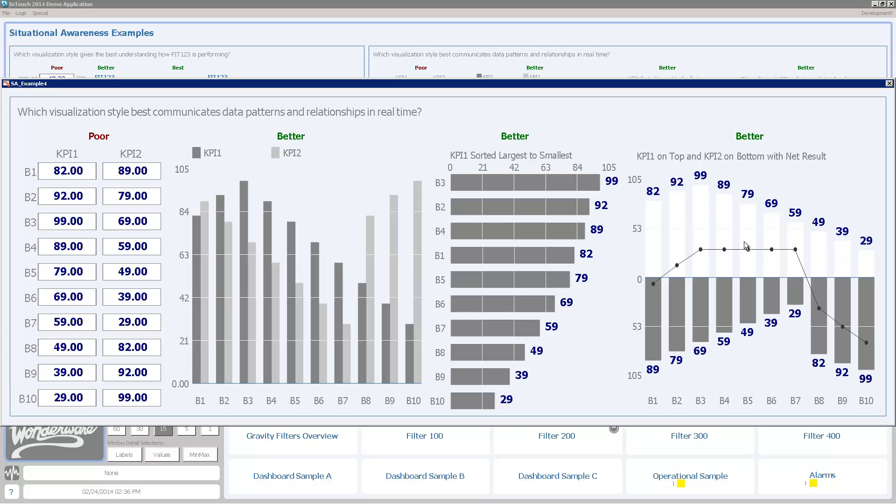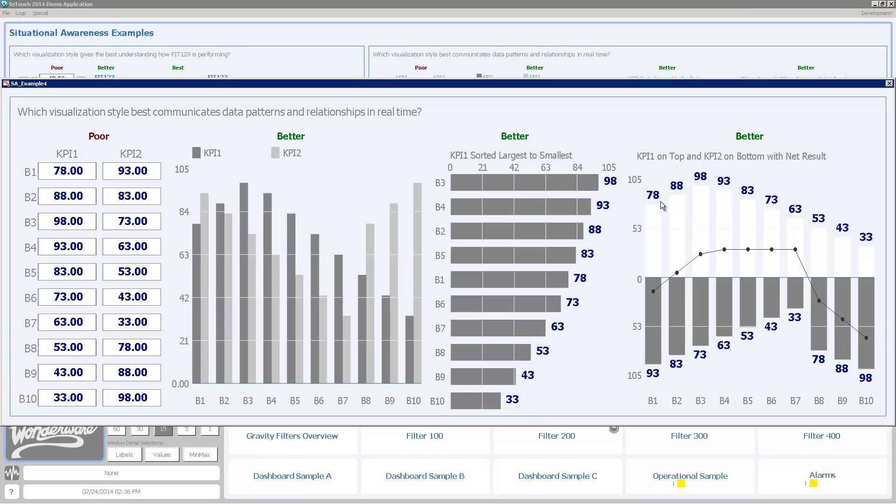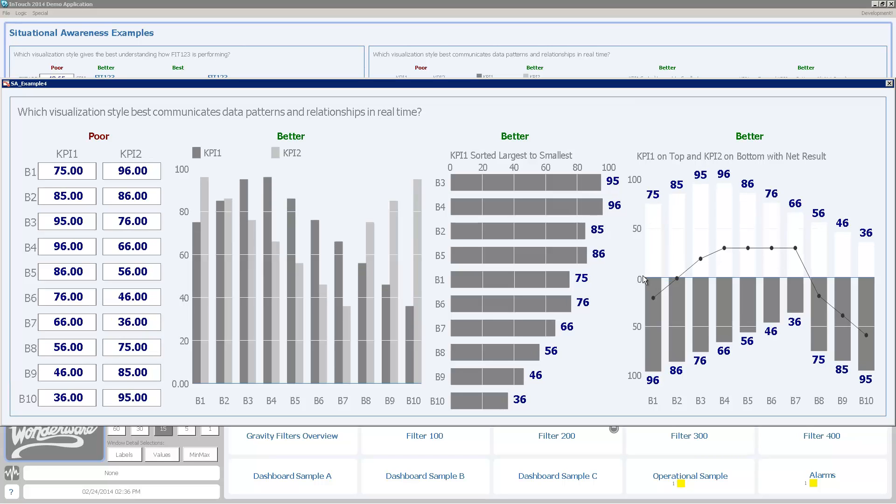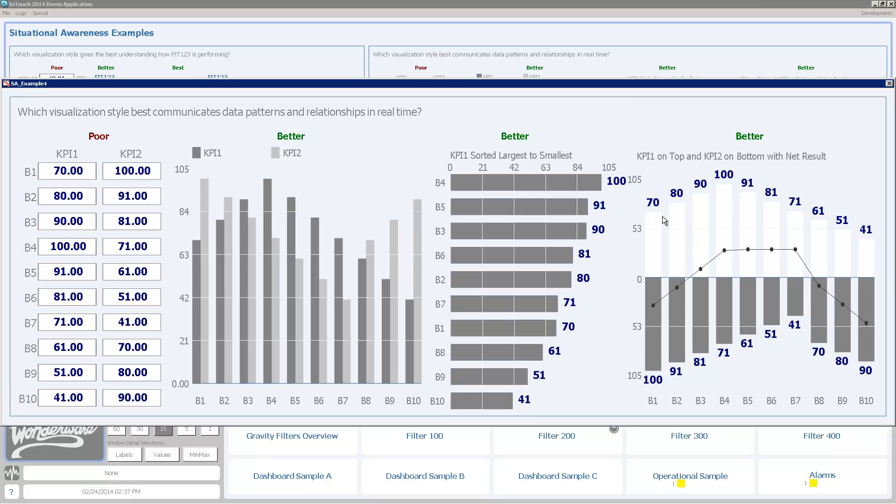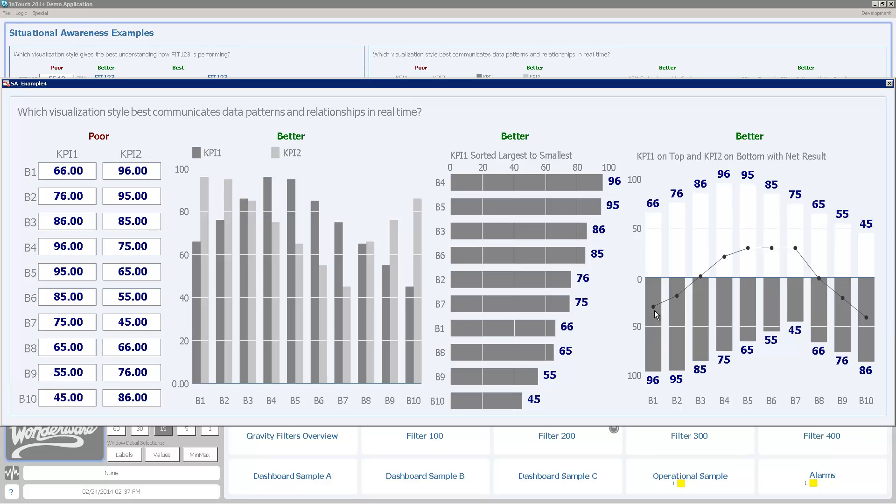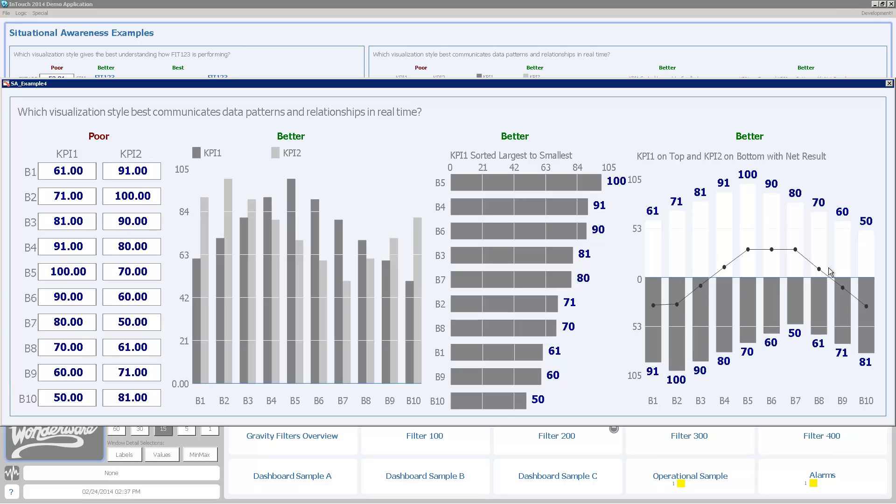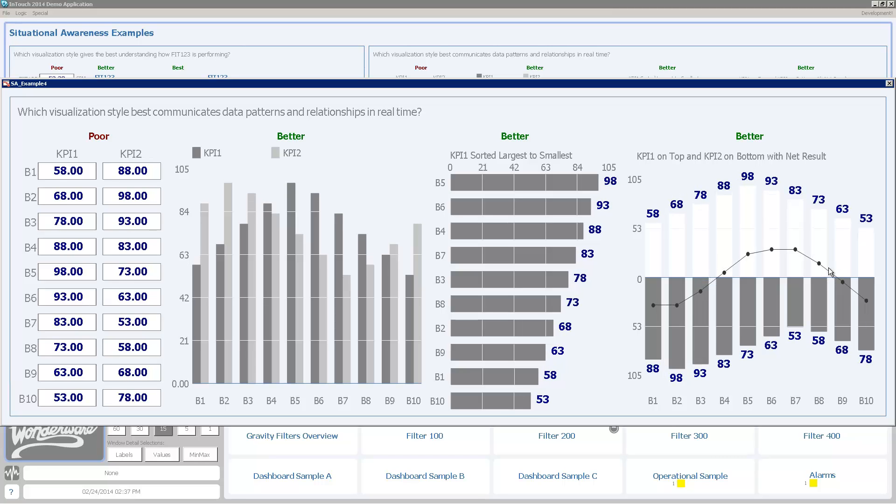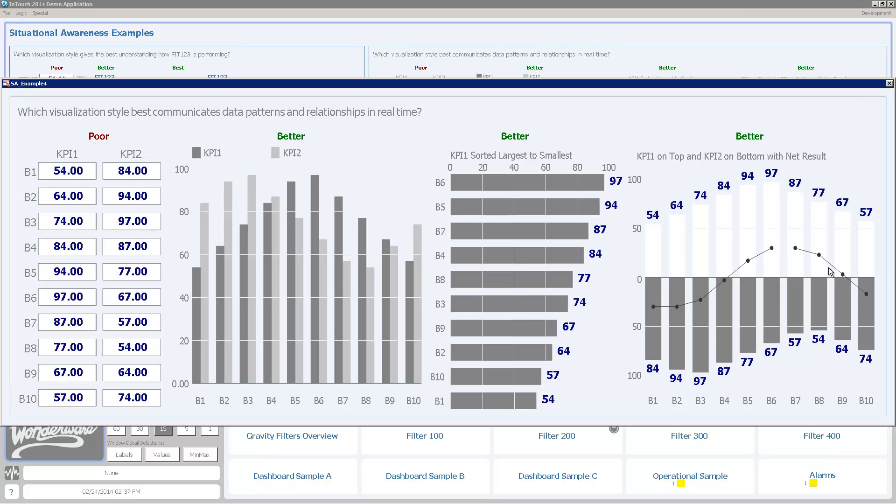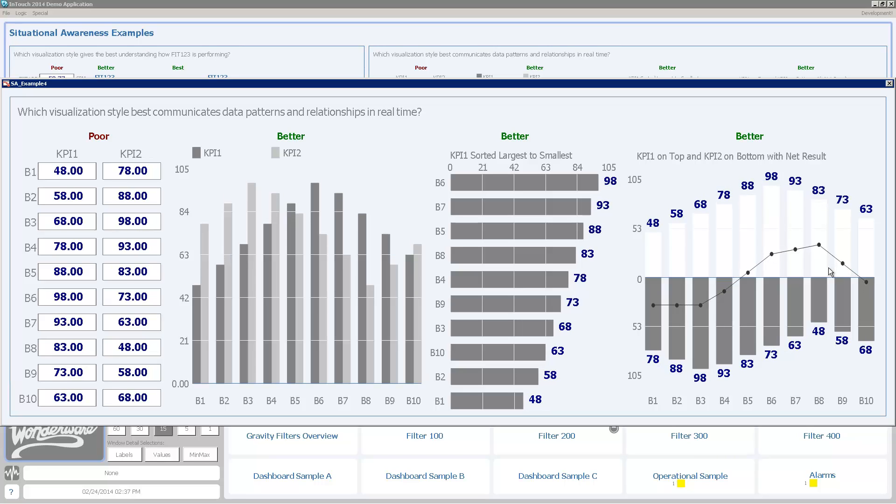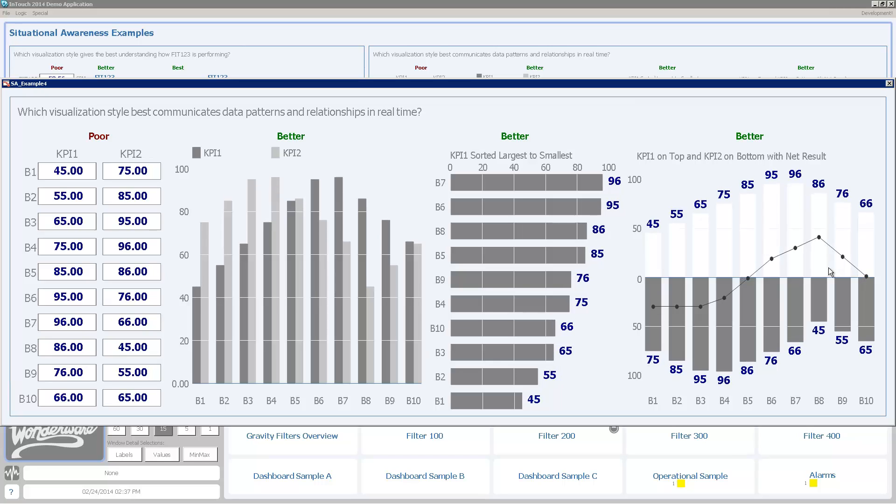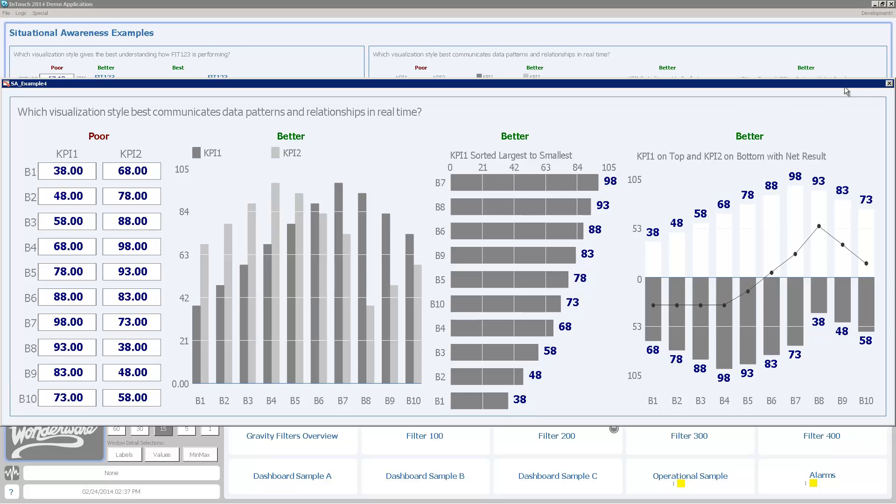Here I'm actually showing how I can look at how these things relate to each other. If I'm trying to understand the difference between values KPI 1 and KPI 2 and look at them across the system, I've got this gain loss chart where I can see where my gains are on the top and my losses are on the bottom, and this line is showing me the net result. Not that these individual techniques are going to be something that's applicable in all situations, but to state that if there is something that you want your operator to be aware of, if you provide a visual technique which makes it easy to assess that, then you'll be able to take an inexperienced operator and make them as effective as a very experienced operator, or even more effective, by using some simple visualization techniques such as these.